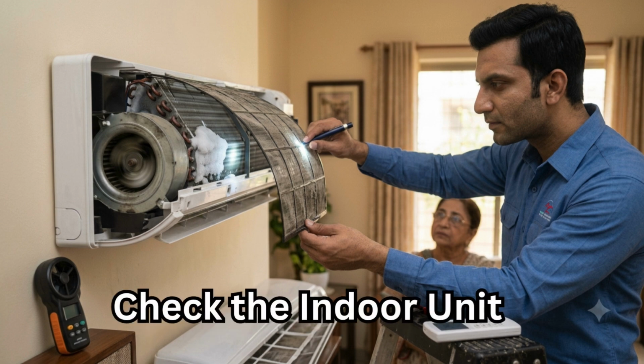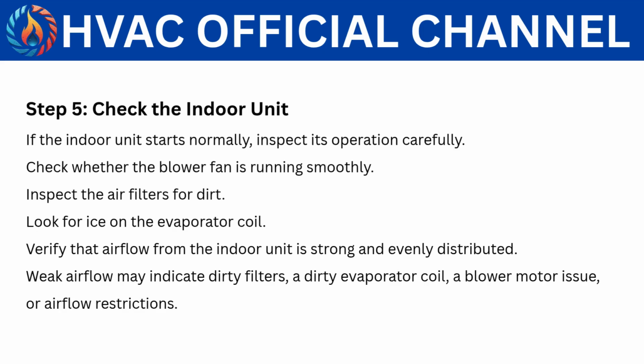Step 5. Check the indoor unit. If the indoor unit starts normally, inspect its operation carefully. Check whether the blower fan is running smoothly. Inspect the air filters for dirt. Look for ice on the evaporator coil. Verify that airflow from the indoor unit is strong and evenly distributed. Weak airflow may indicate dirty filters, a dirty evaporator coil, a blower motor issue, or airflow restrictions.